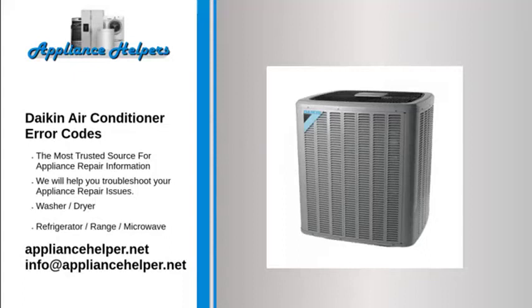Code A9. Problem: malfunction of electronic expansion valve drive. Defect of electronic expansion valve coil. Defect of indoor unit PCB. Defect of connector contact.